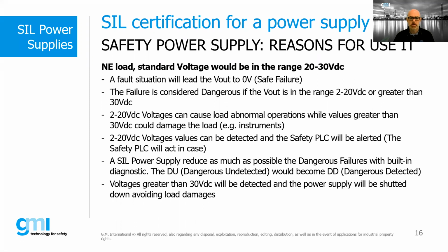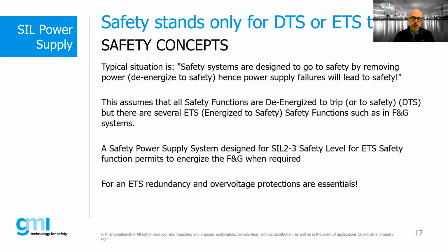Thank you, Andrea. Next slide. Now we introduce the concept of safety power supply applied to a typical application as DTS or ETS, de-energized to safe or energized to safe. As we know, typically the safety systems are designed to remove power to the system in case of the de-energized to safe application. Therefore, the failure of the power supply, which goes to 0 output voltage, is considered a safe failure. So we assume that all safety functions are DTS or DTT, the de-energized to trip type.